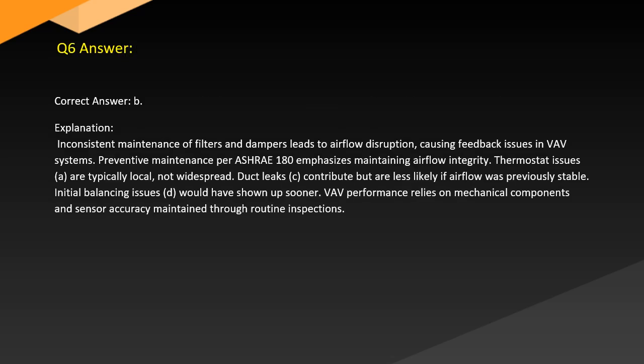Answer. Correct answer: B. Explanation. Inconsistent maintenance of filters and dampers leads to airflow disruption, causing feedback issues in VAV systems. Preventive maintenance per ASHRAE 180 emphasizes maintaining airflow integrity. Thermostat issues are typically local, not widespread. Duct leaks (C) contribute, but are less likely if airflow was previously stable. Initial balancing issues (D) would have shown up sooner. VAV performance relies on mechanical components and sensor accuracy maintained through routine inspections.